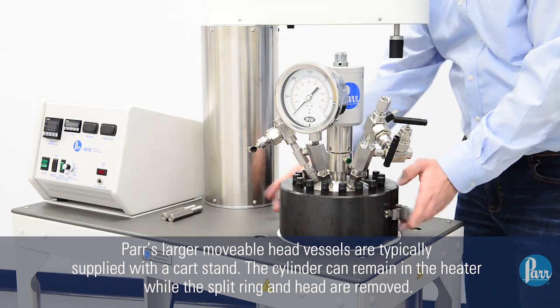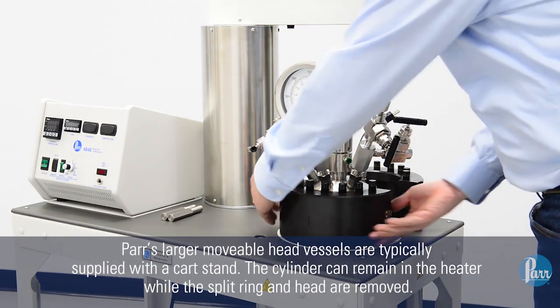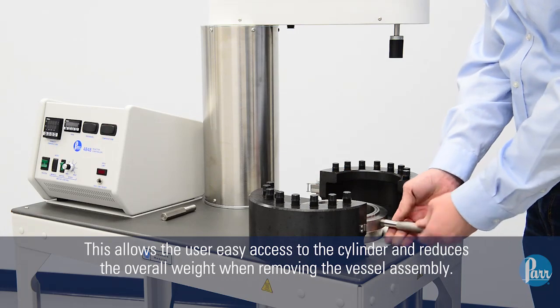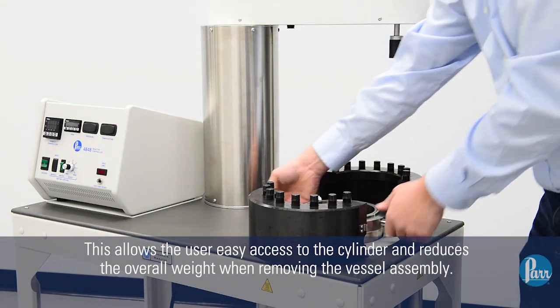Parr's larger movable head vessels are typically supplied with a cart stand. The cylinder can remain in the heater while the split ring and head are removed, allowing the user easy access to the cylinder and reducing the overall weight when removing the vessel assembly.